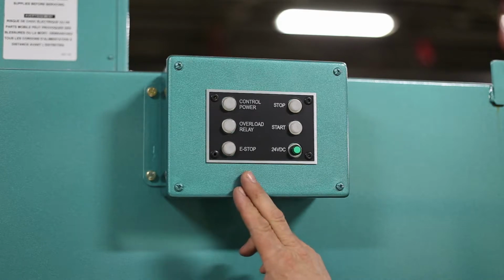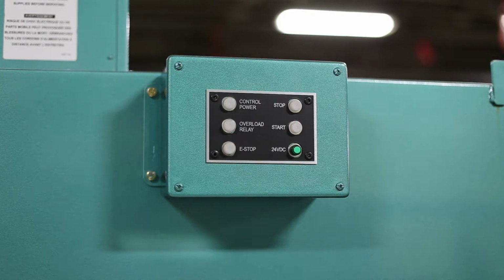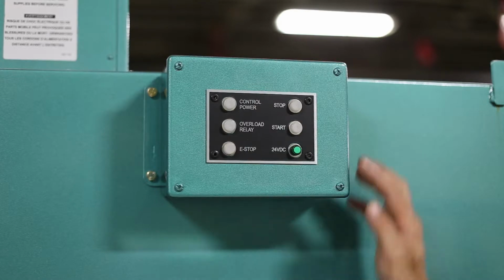First, if there's no lights on at all, and your switch is turned on, your control transformer switch is turned on, we got to go take a look at the control transformer. So let's go take a look at your control transformer so you're familiar with that.